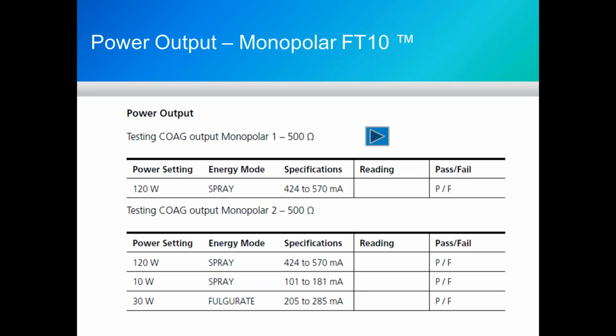So looking at the service manual, it will have you do a power test on Monopolar 1. We're going to do coag spray at the maximum output setting of 120 watts. And we're going to be looking for a current between 424 to 570 milliamps being the target. A lot of your generators will do pass-fail based on power output. That power output is typically plus or minus 15, or more typical, plus or minus 20%. For the Valleylab products, they have settled in and will use current as the pass-fail mechanism.